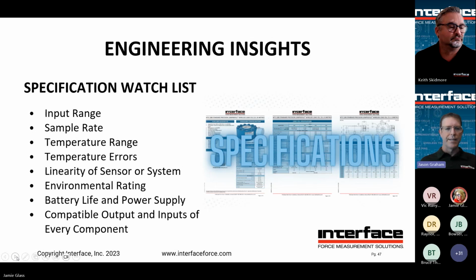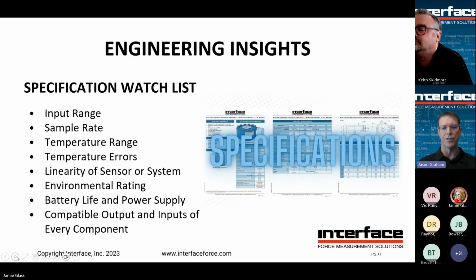In some cases we may have a temperature range for the wireless device. You look at, is that acceptable? Can it be used outdoors? What are the potential temperature errors based on the environment that device may be in? Environmental ratings: inside, outside, submerged, not submerged, ATEX or safety, some secure ratings.